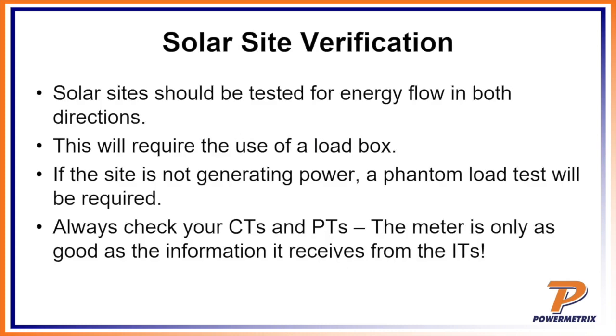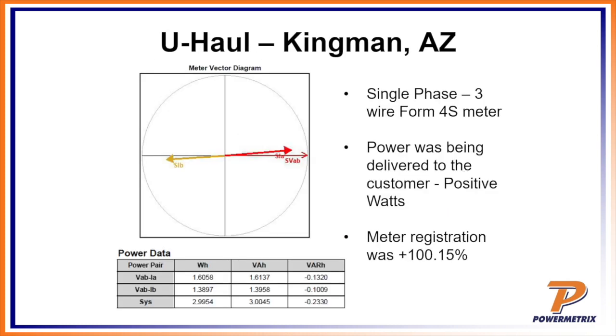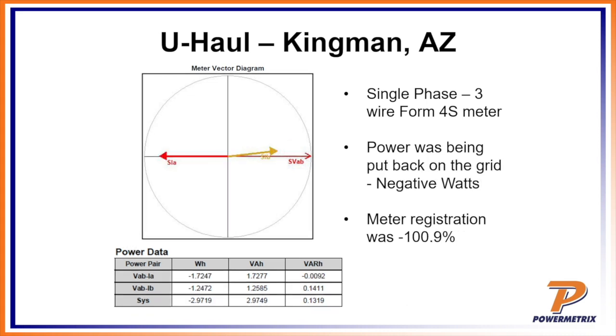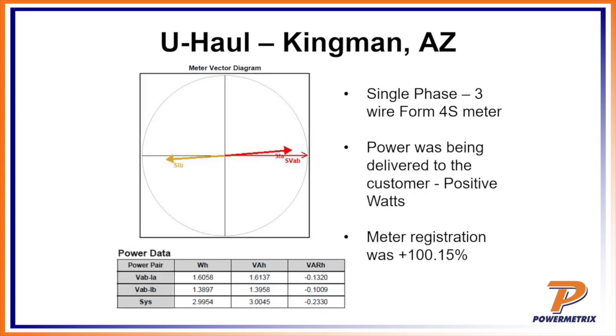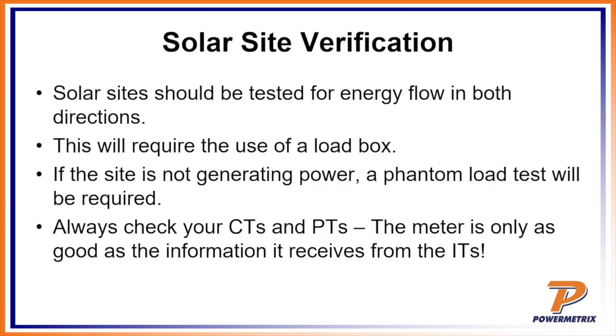Like I mentioned with this 3S and this 4S meter, you got positive, then you got negative. You got negative energy flow and positive energy flow. So this is on customer load conditions. We do recommend that you want to make sure that meter is correctly measuring power, both received and delivered.